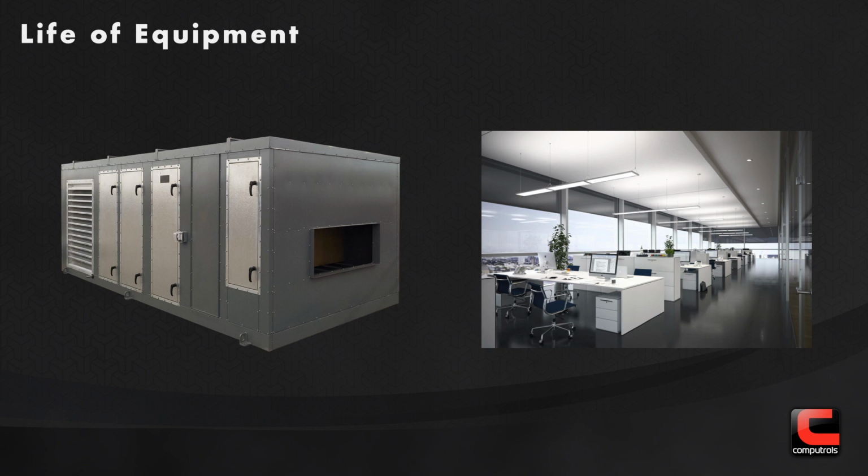And then we look at the life of equipment and how building automation systems can affect this and affect really how much maintenance you need on this equipment. So I think we've all run into a situation or heard of a situation where you were recommissioning or retro-commissioning a building, and you find out that the building automation system is giving you bad data. So it says that your air handler or your light fixtures are off, and they're going off at 6 p.m. every day per the schedule that you put in there. But then you go and commission the building, and you see that it's continuing to run overnight.